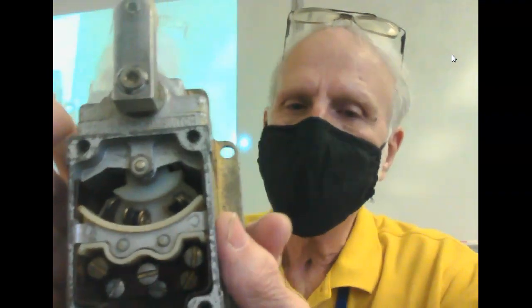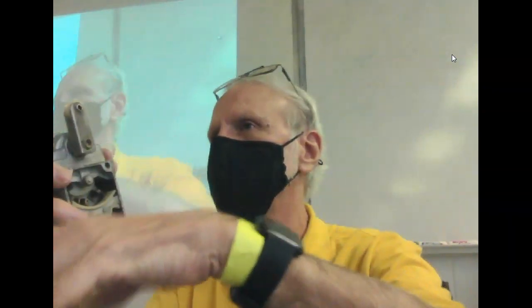But these things are very, very reliable. Like I said, if you take care of them, the biggest problem we have is people mounting them wrong, and then whatever they're trying to measure takes the operator and sends it too far and breaks it and stuff like that.